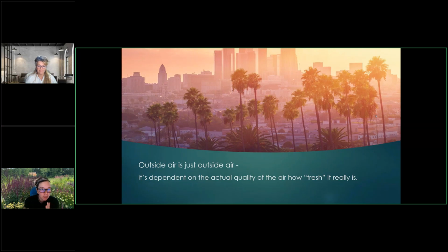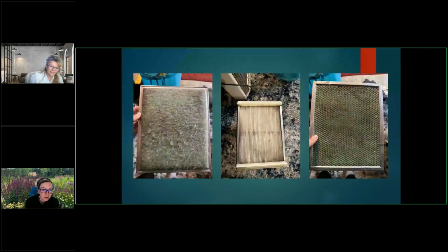And then you have filtered air, which is taking this and running it through some kind of filtration system. And that's what we would consider the most fresh air. So this is a picture of an ERV core outside, wildfire smoke kind of coming in here. It's actually wood stove smoke from someone who didn't burn dry wood or didn't make hot enough fires.